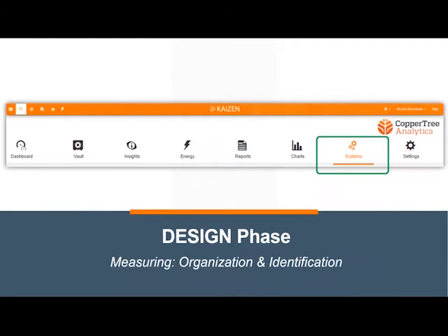Design phase, organization and identification. During the design phase and just before the next phase, when functional verification begins, there is the need to first identify the point function, and secondly, organize the building automation system points into systems. At this stage, data organized into systems is fundamental to the functional verification of systems, which are groupings of pieces of equipment with sensors and control devices. Since the system graphics aren't typically available at this stage of the project, analytics can really help to bring the HVAC system into perspective.